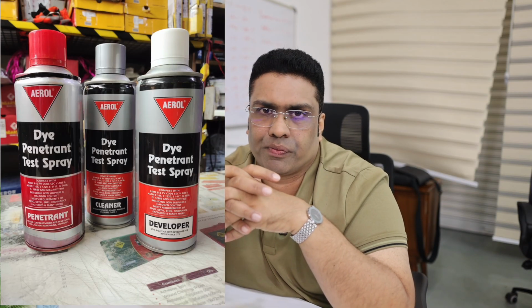In that situation, practically we do two types of testing. First, the welding joints DP test, dye penetration testing. And the very important thing is that after dye penetration testing, sometimes a leak may still occur. There's a chance. Because when we are commissioning the chilled water system, almost all the area ceiling, false ceiling is completed. In that situation, we are entering testing and commissioning. In such a situation, it's better to do it with compressed air. That's what we were doing in our construction industry. DP test, of course, we will do for the big size pipes. And there are big compressors. Bring them or rent them and do the testing with the help of compressed air. And after the compressed air testing, it's okay.